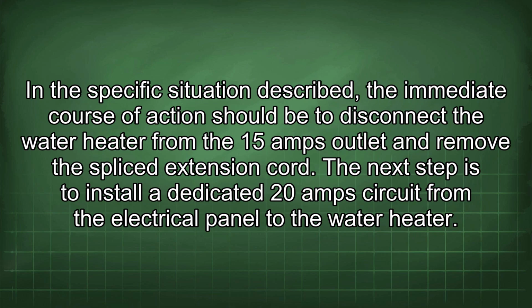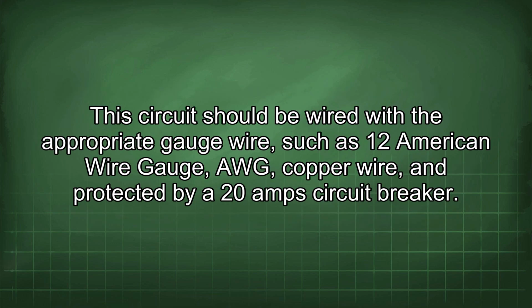In the specific situation described, the immediate course of action should be to disconnect the water heater from the 15 amp outlet and remove the spliced extension cord. The next step is to install a dedicated 20 amp circuit from the electrical panel to the water heater. This circuit should be wired with the appropriate gauge wire, such as 12 American Wire Gauge copper wire, and protected by a 20 amp circuit breaker.